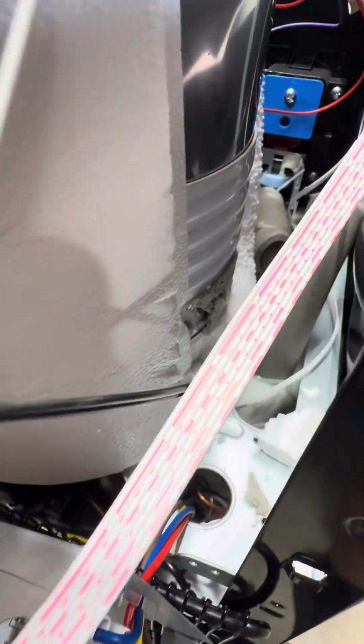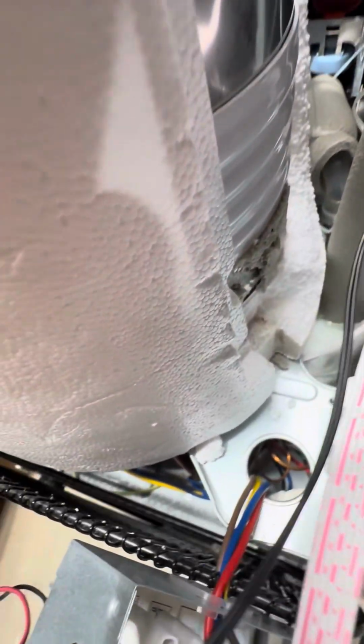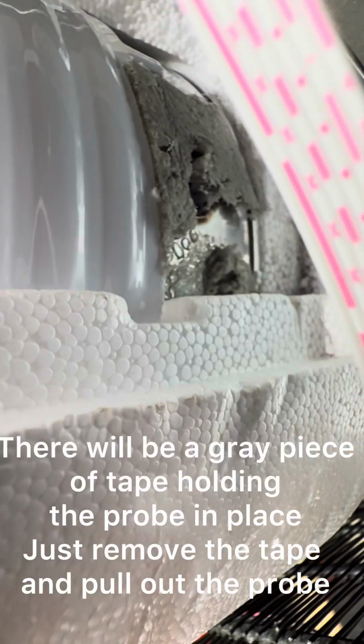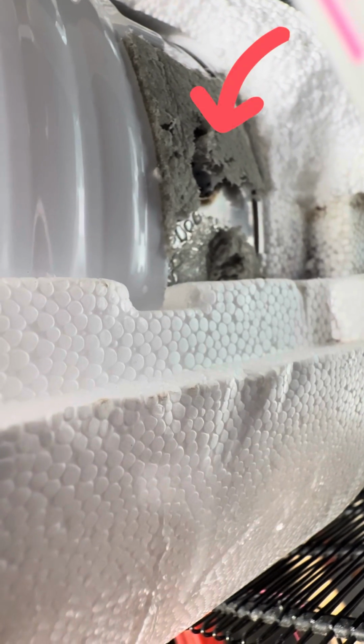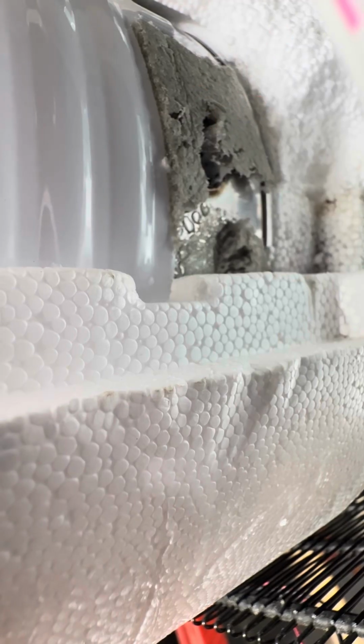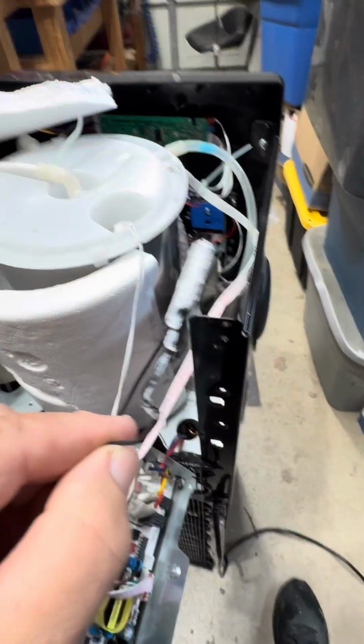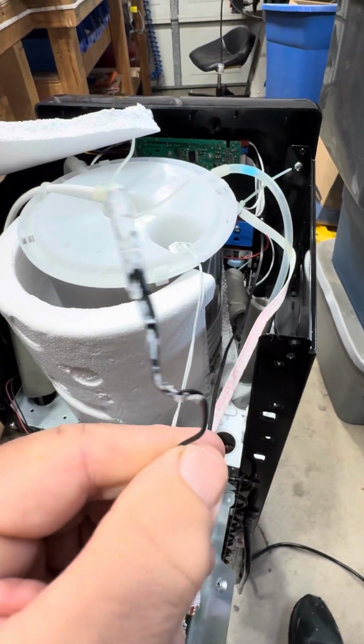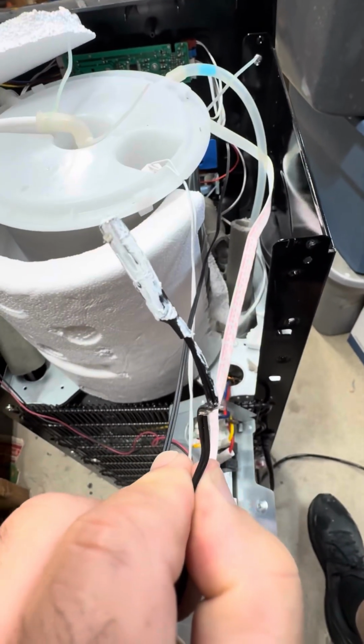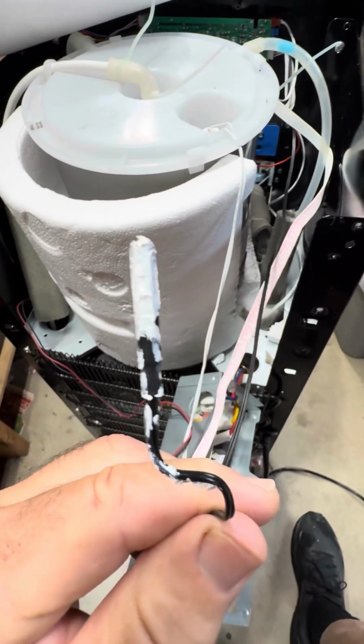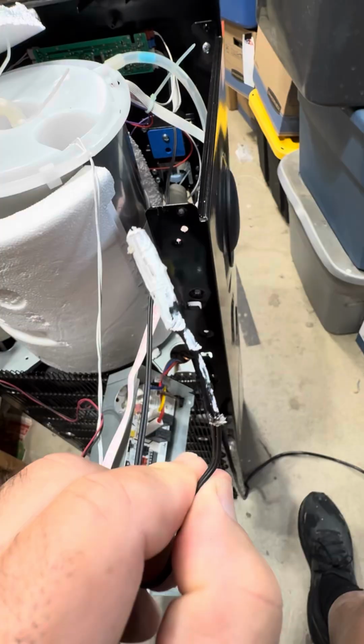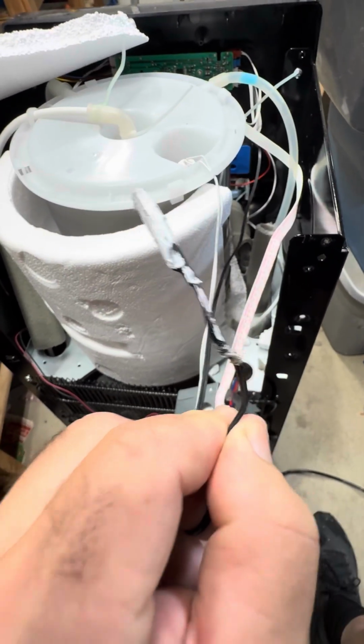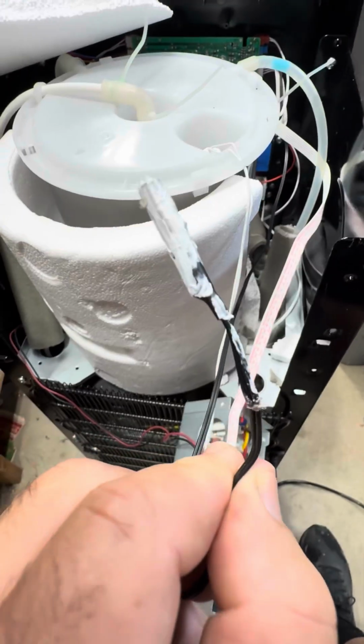It's going to be kind of hard to see, but as you can tell, I'm going to get my camera down in there. There is a hole on the side of the chamber that essentially the probe went into. It is not a sealed unit, so when you remove the probe, there won't be any water leakage, so you don't have to worry about that. It's in a small chamber, and it's basically held into position with what they call thermal lithium grease. It's conductive for thermal. It aids in allowing the temperature of the water to successfully contact the probe to give accurate temperature results. So exactly what is this probe? Okay, well, next section I'm going to explain that a little deeper.